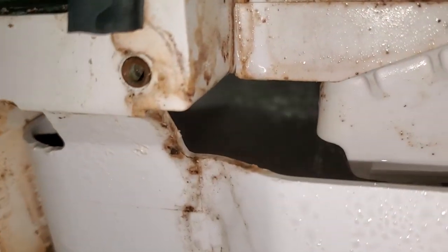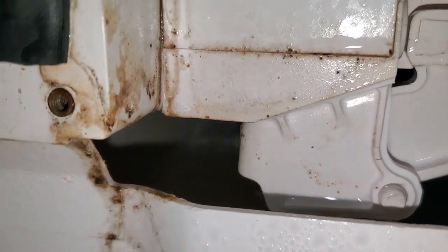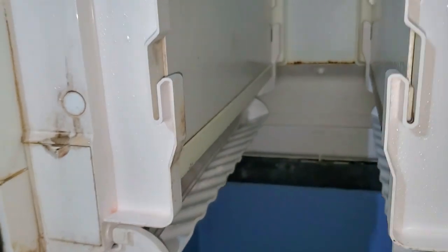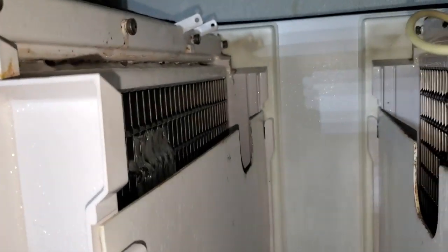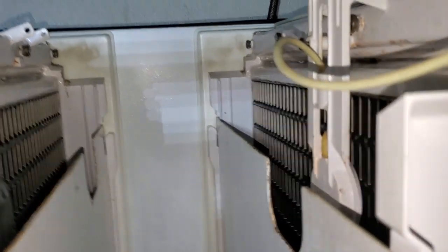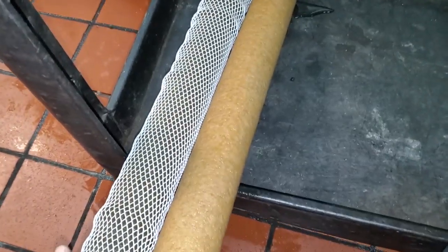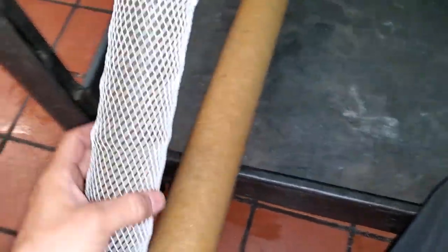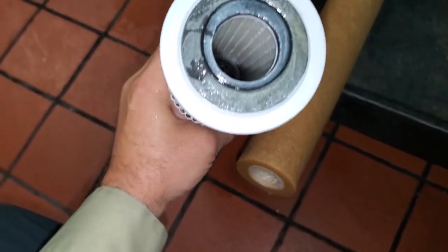Now you can actually hear it flowing into it. So yeah, definitely low water flow, low water pressure. We'll continue to diagnose past that point. Here's the filters, and they're just plugged up internally, the jacket's all discombobulated.